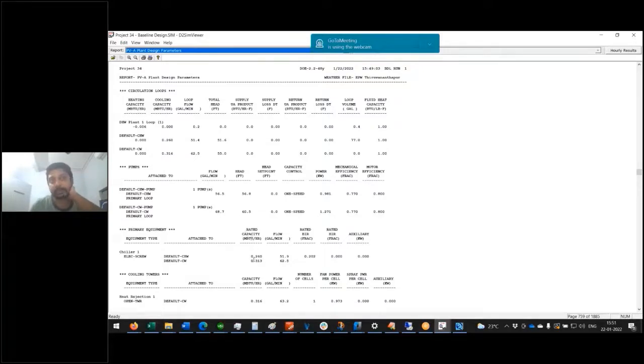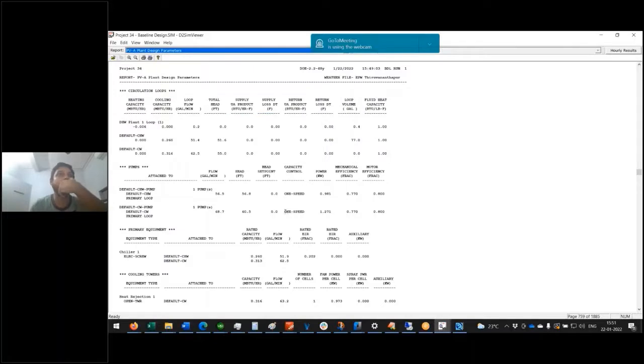Here you will get the rated capacity. Right. I'm sorry. Yeah. So you have to go to PVA, not PST. Okay, so here you will get the cooling capacity of default CHW, which is 0.26 MBTU per hour. You can see both even under circulation loop and even under the chiller. Don't take the capacity of condenser water. Condenser water capacity will always be greater than chilled water capacity. So when we define tonnage, we define it only for the rated capacity, okay, for the chilled water loop.